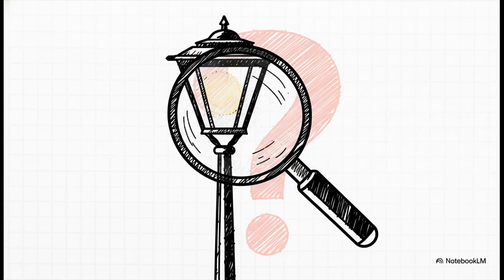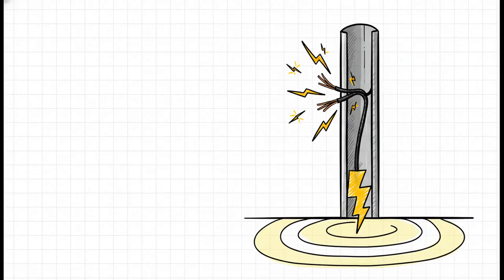All right, let's put all the pieces together. Let's go back to that streetlight from the beginning. Now that we know all this, let's see exactly how that seemingly harmless object becomes so dangerous. The story starts with a single fault. Maybe the insulation inside the pole has gotten old and worn through, and a live wire is now touching the metal pole itself. That pole is earthed, so now current is pouring into the ground, creating invisible voltage ripples spreading out from the base.